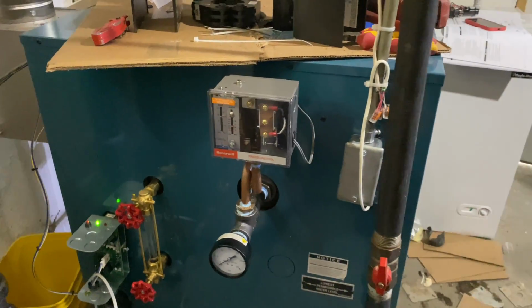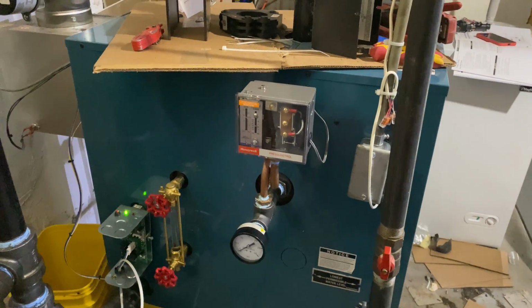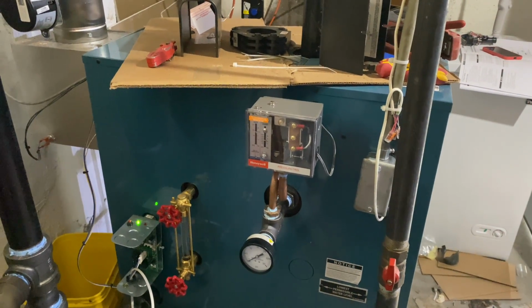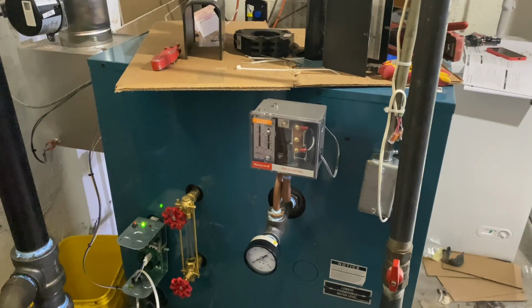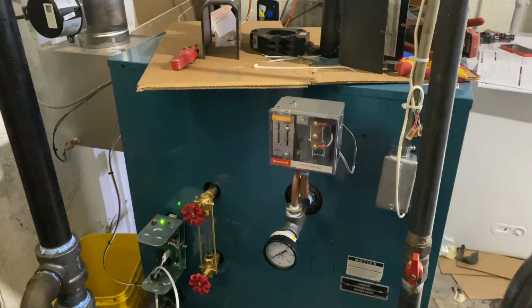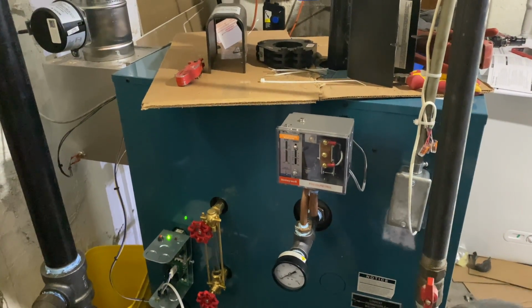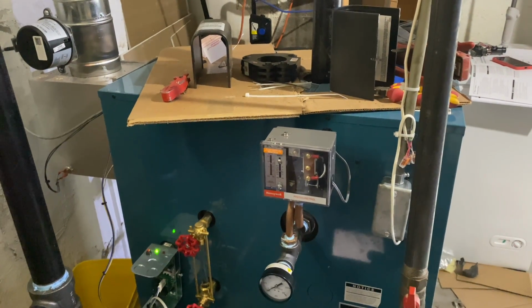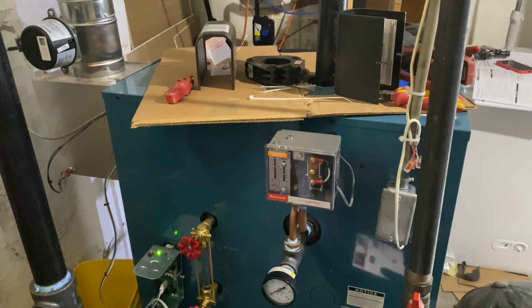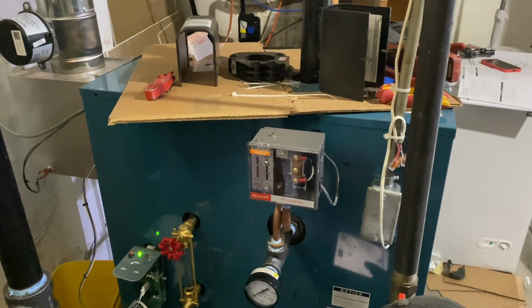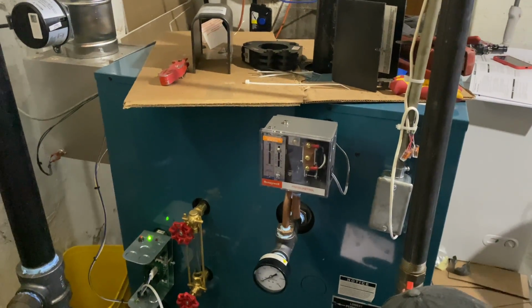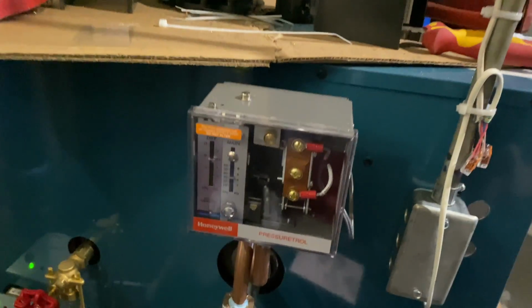You raise up that Pressuretrol, you're going to have other issues. You're going to have banging of pipes. You're going to have excessive fuel bill. You're going to have possibility of older steam radiator valves, air valves, letting out steam because they're on their way out and they're not designed to hold back all that pressure. But US Boiler recommends where it is right now. Just saying.